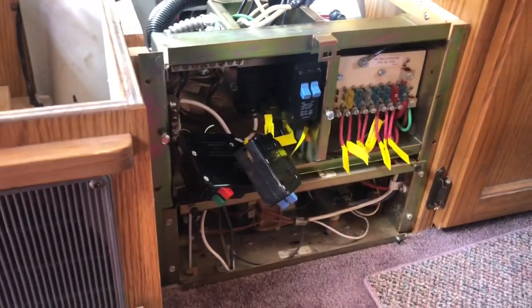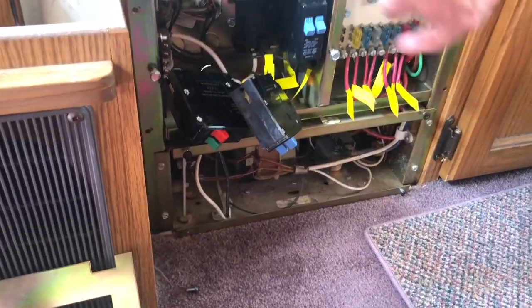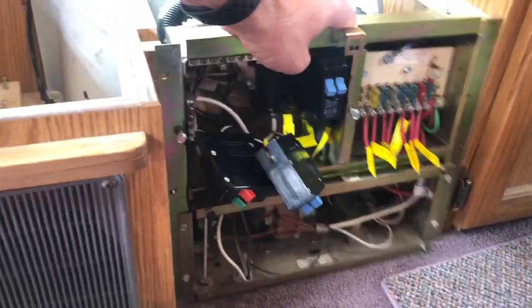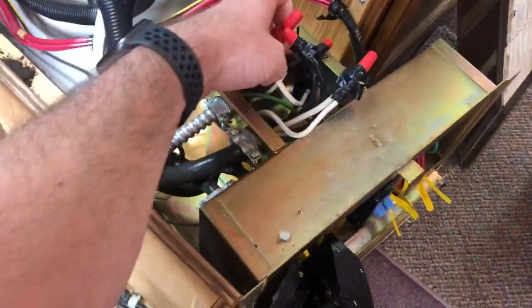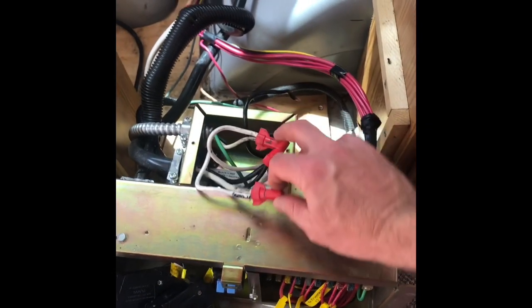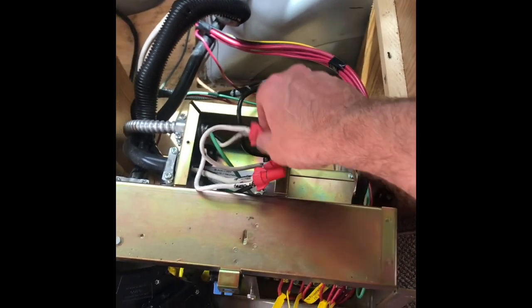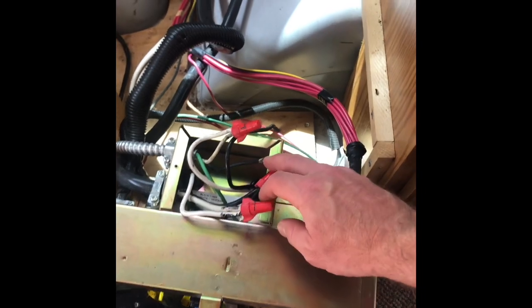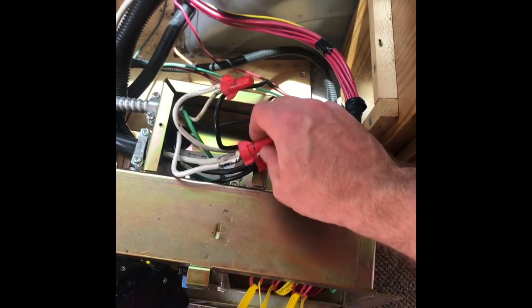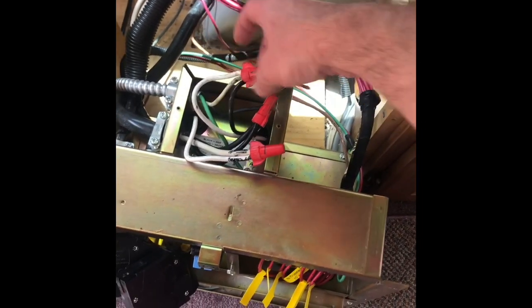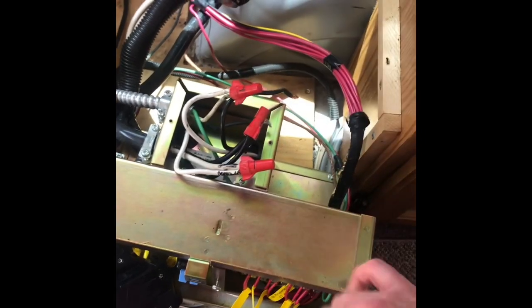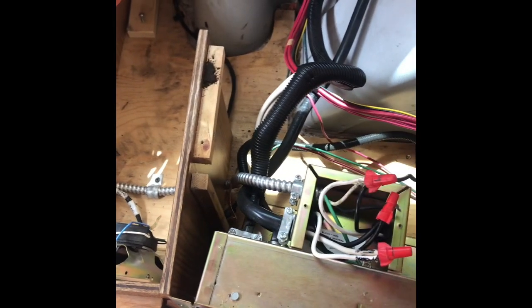So at this point we've gone through and removed the 4 mounting screws on the front. We're gonna go ahead and pull it out, and we're actually gonna start disconnecting the wires from the automatic transfer switch. A real good idea for this is to take one or multiple pictures of that to make sure you know where the wires are going, and actually label the wires as to how they go, because we're going to have to pull this off since there's a separate line coming in for the generator feed, so we'll probably have to move this thing over a little bit.